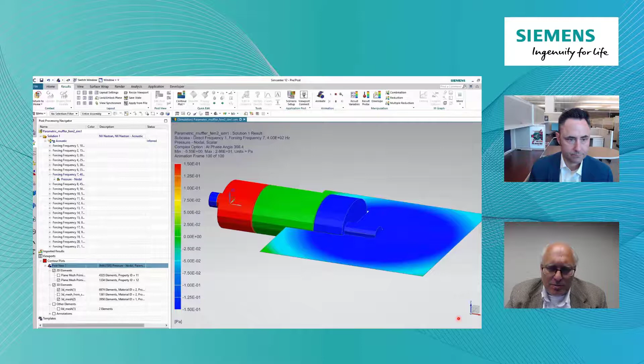So those are some muffler applications. Some other ways we can control sound in terms of duct acoustics. One of the tricks here is something called a Helmholtz resonator. And this is an additional acoustic volume that you put on your duct to try to control noise at a specific frequency. And if you're familiar with a tuned mass absorber from a vibration standpoint, you know you have a mass and a spring tuned to a specific frequency. This Helmholtz resonator is exactly the same principle.